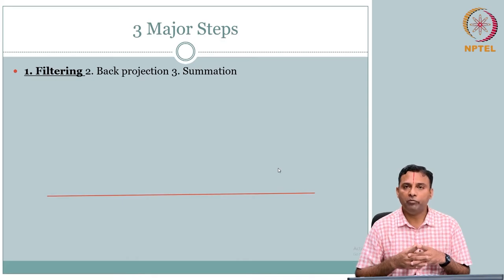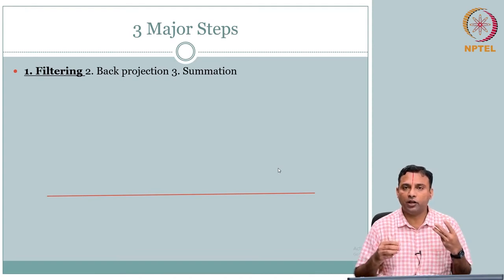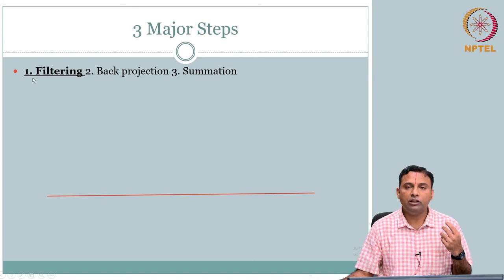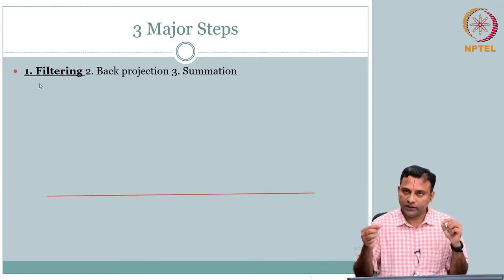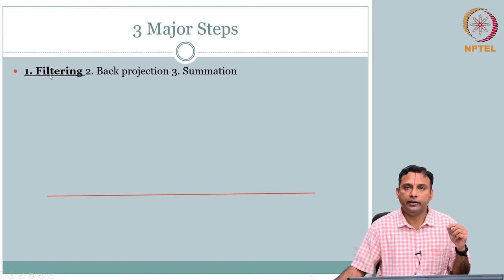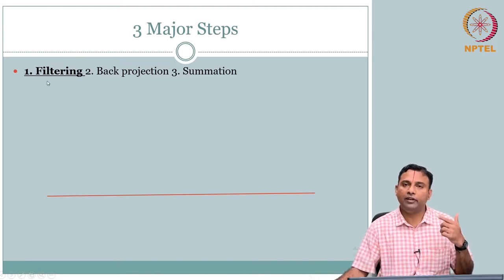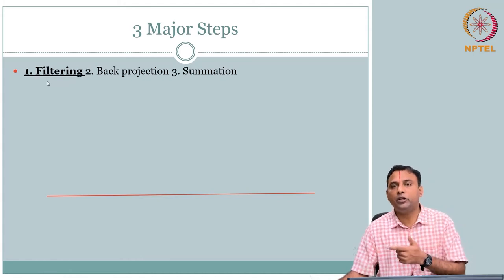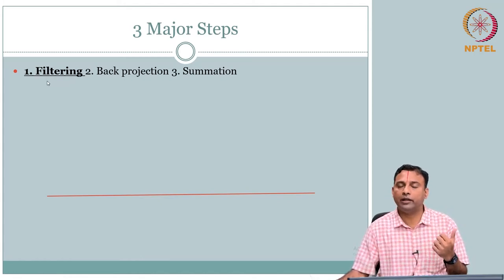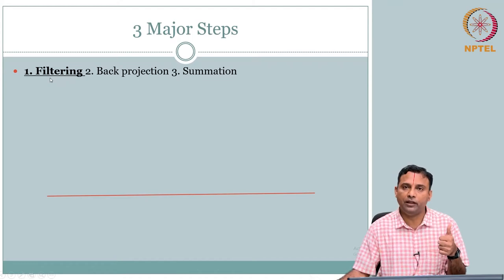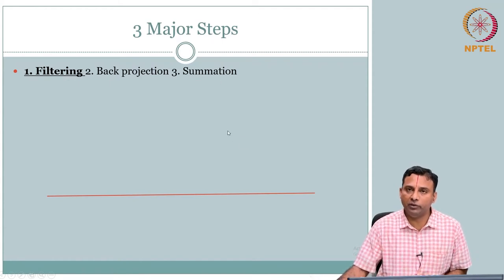Before we move on, let's recap. We have three major steps in this reconstruction that we saw so far. First is filtering — you get your data acquisition as projections, and that projection data has to be filtered. Filtering can be accomplished in the frequency domain or in the time domain, which came as filtered back projection or convolution back projection. Filtering is the first step after you collect the raw data, and then you have to do back projection. Finally, summation. So these are the three major steps.